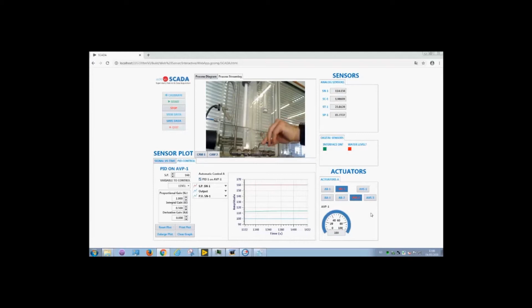As the system includes several cameras, it is possible to change the view among them and watch if the process is behaving as we expect. If you observe the graph or the level of the tank, you will see that the set point is being reached. Once the set point is reached, the proportional valve AVP1 is decreasing steadily and it will reach zero value in order to keep the desired set point. If there is an overshoot in the action, it causes that the level of the tank goes beyond the established set point. Such effect can be minimized adjusting the PID gains, although the PID control will manage to stabilize it.